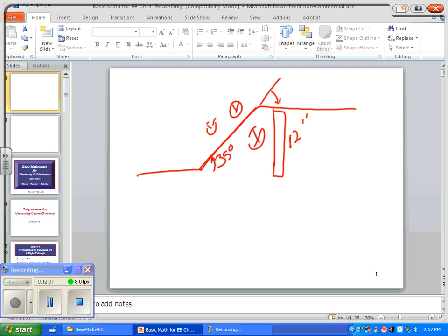And if you flip it over properly, it won't have what's called a dog leg, and it'll look just perfect. It'll go straight down the run, and it'll go up, it'll go back to level, and it'll just look perfect. It'll be a great thing. But what we need to know when we're bending conduit is how far between the marks do we need to bend it? What's the distance between these two 35-degree bends?